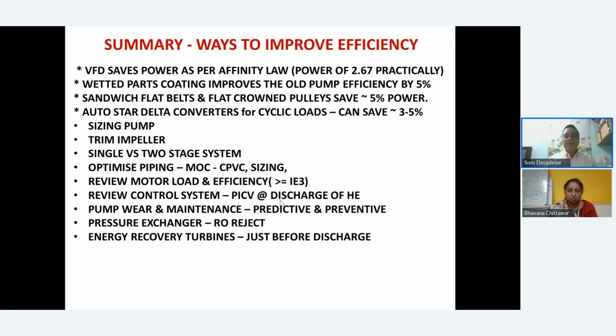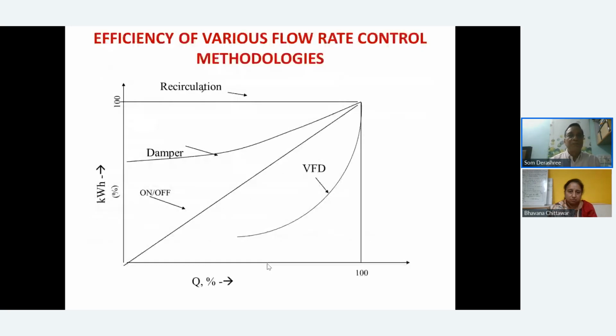You should have that looping system to have the same travel path for suction, discharge, or all flows. We'll see one of the applications here. And then pump wear maintenance, predictive and preventive maintenance, to be there. Pressure exchangers. This is a new, like heat exchanger. Pressure exchangers have also come into foray now, introduced by some of the manufacturers. We'll share that. And pressure recovery turbines also have come in. So let's see what these are.